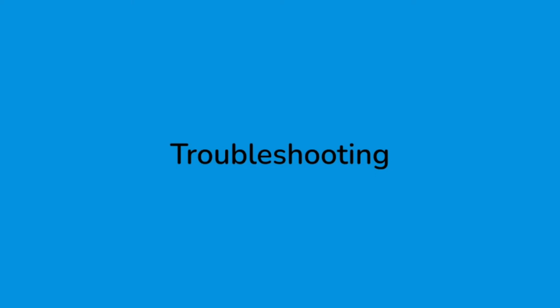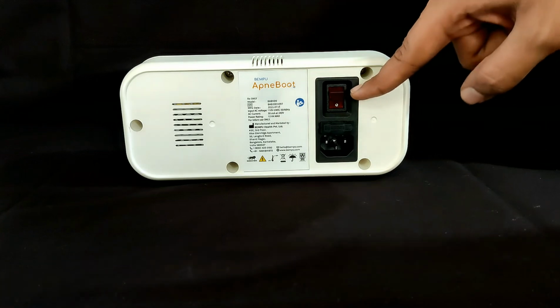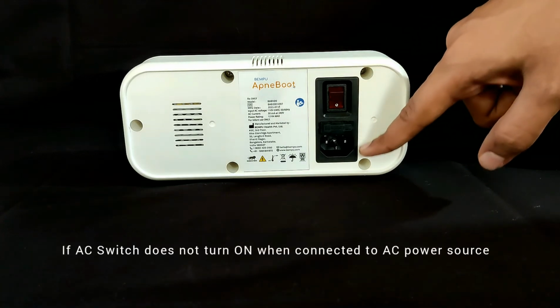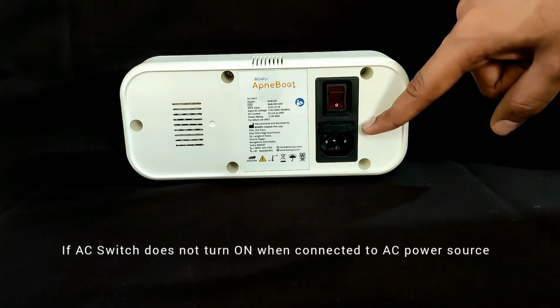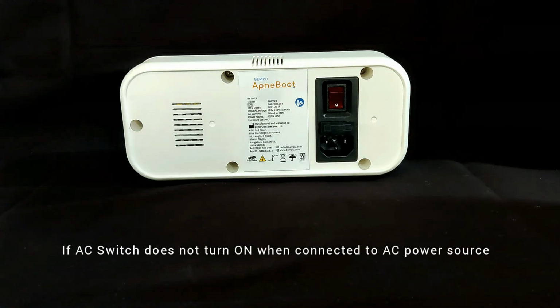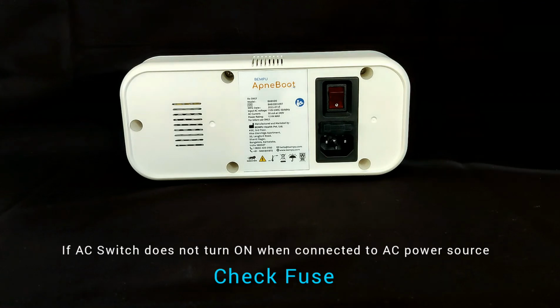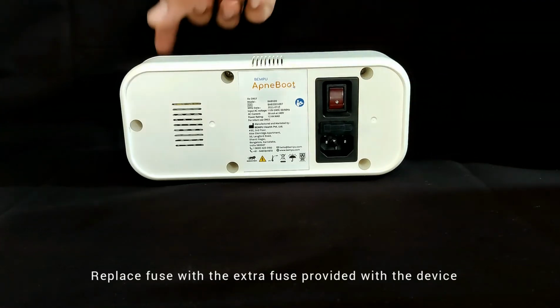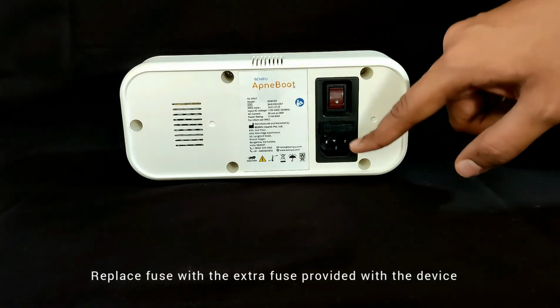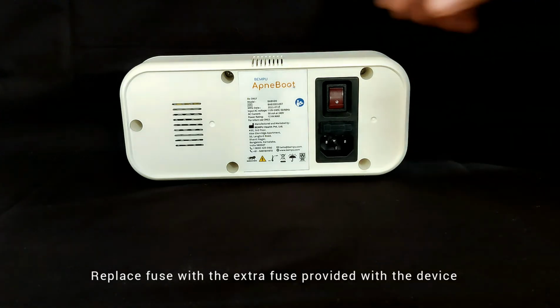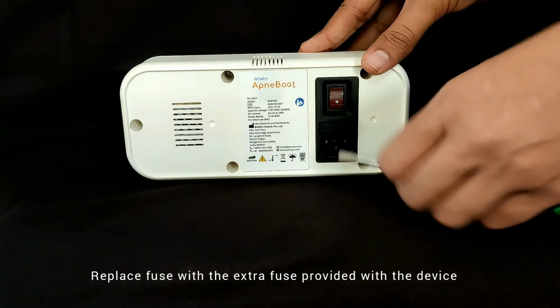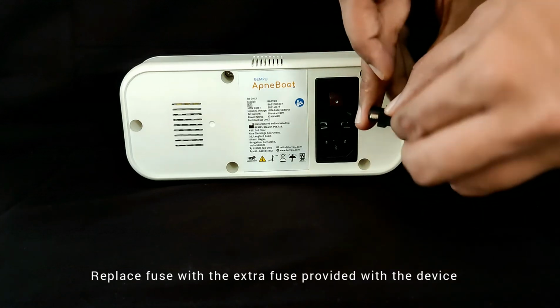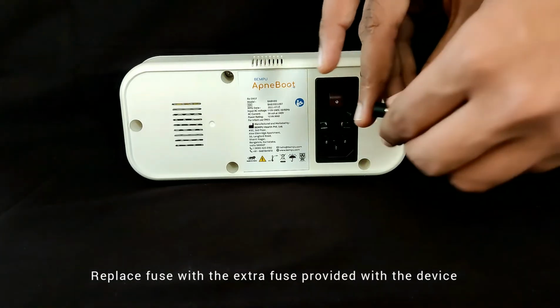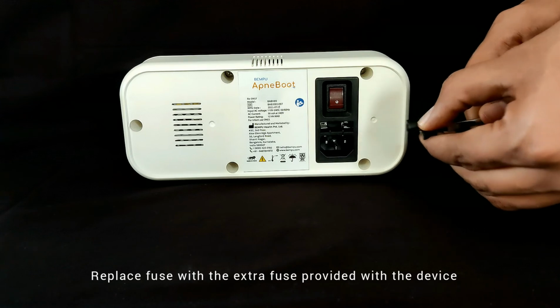Here are some of the troubleshooting steps you can try in case the device stops working as intended. If the AC power switch does not glow red when connected to AC supply, it's possible that the fuse is blown. So please check the fuse and replace it with the extra fuse provided. To do so, switch off the AC power switch and the power button. Disconnect the power cord from the device. Pull the fuse holder with the help of a screwdriver as shown. Remove the blown fuse and replace it with the extra fuse provided.